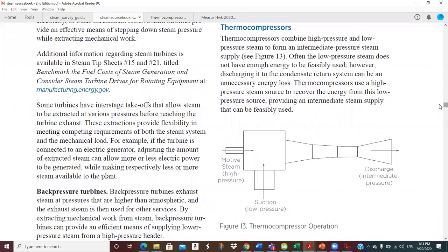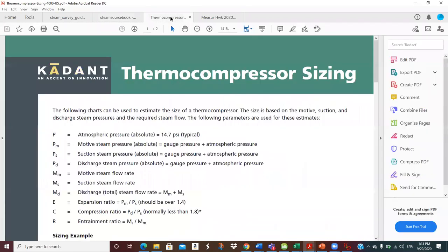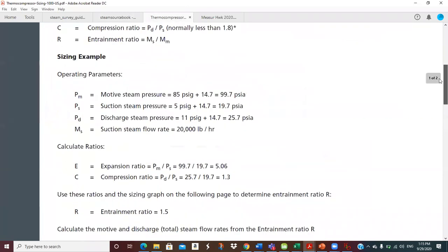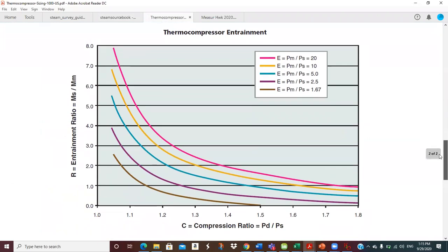If this suction — this low pressure — we could set that right on top of that atmospheric pressure tank. This thing is like a Venturi: you put higher pressure steam in the end, it blows through there and sucks that low pressure steam in with it, and the discharge is an intermediate pressure high enough to be useful. That sounds like something we could use in this situation. If we've got 3,000–5,000 pounds of steam consistently being flashed to atmosphere, we might have a project here. We've got three different headers — 30, 180, and 400 pound — so we've got high enough pressure steam to make this work. Where would we like to take this steam? The 30-pound header would be a really good idea.